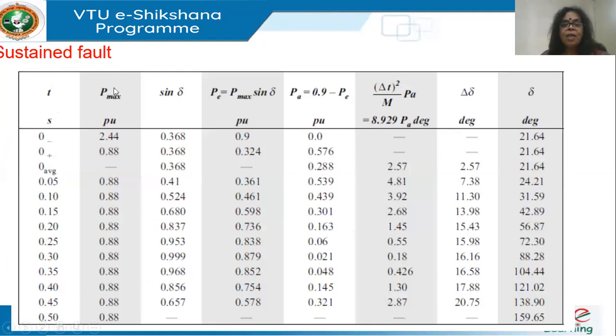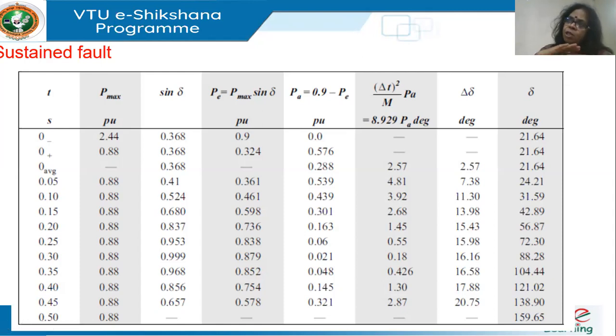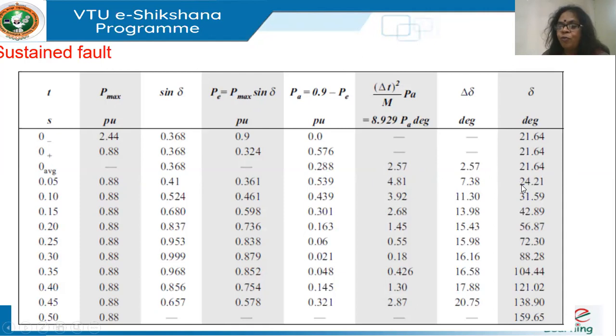For a sustained fault, the fault is never cleared, so Pmax remains 0.88 throughout. Build a table: at 0⁻, Pmax = 2.44; at 0⁺, Pmax = 0.88 for all subsequent steps. Use the average PA only for the first step where the fault occurs. Then calculate the change in angle and add it to the previous angle to get the new δ at each time step. Proceed recursively.